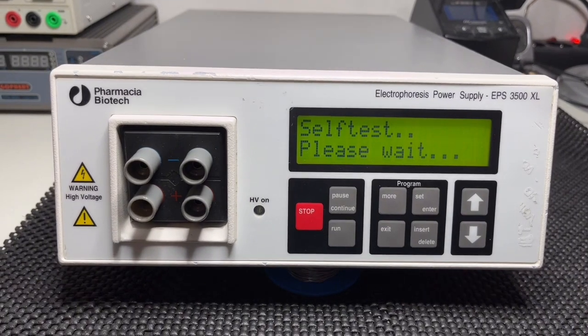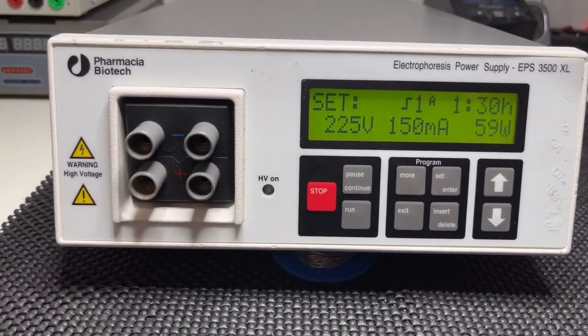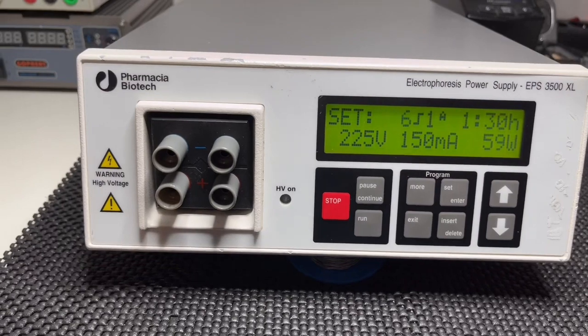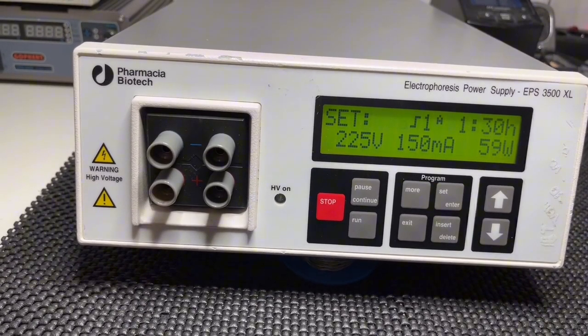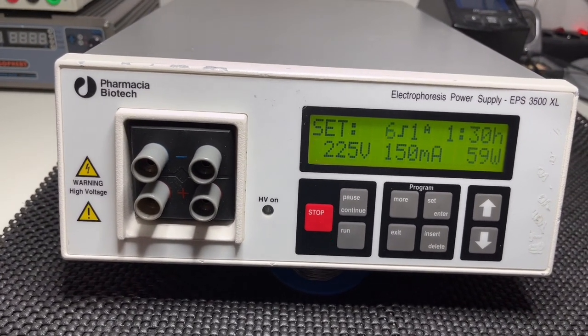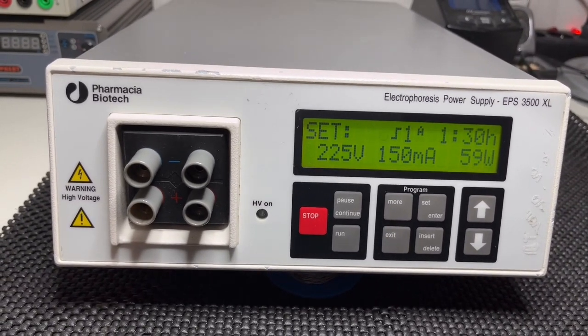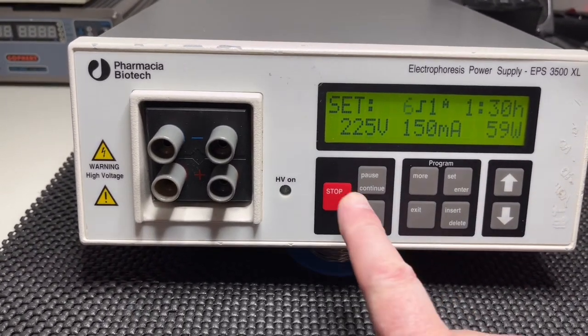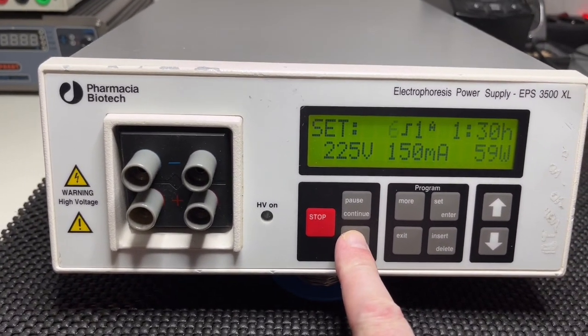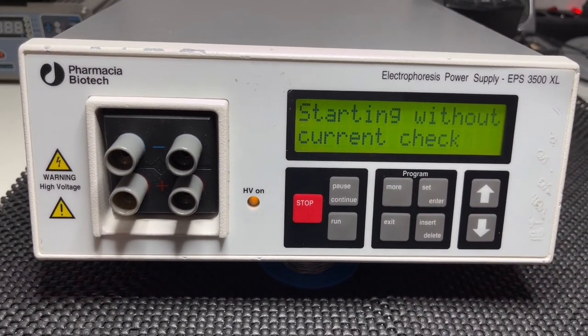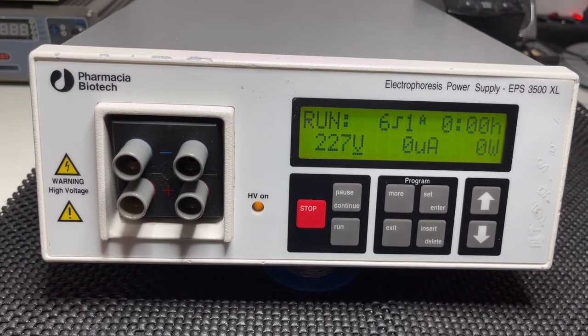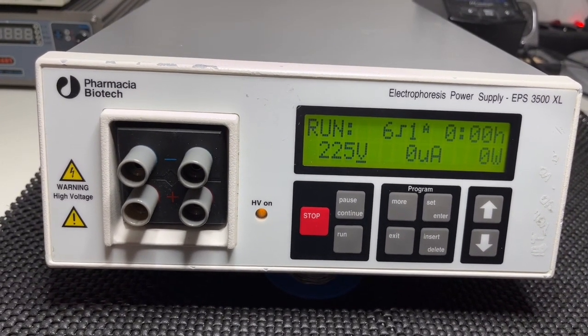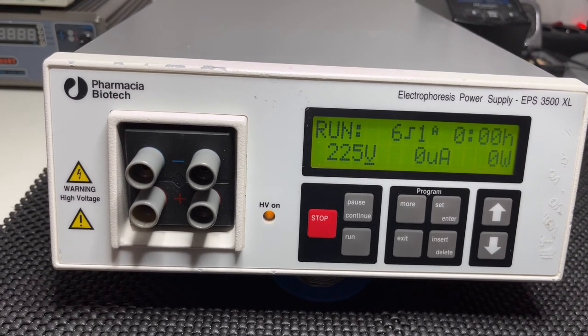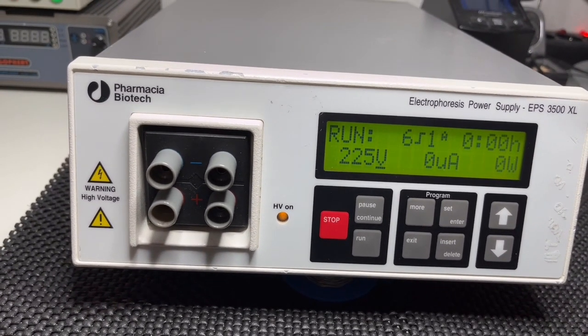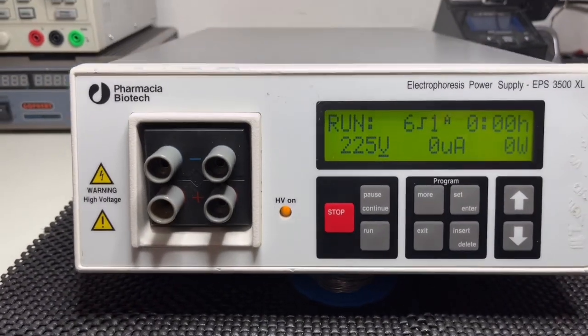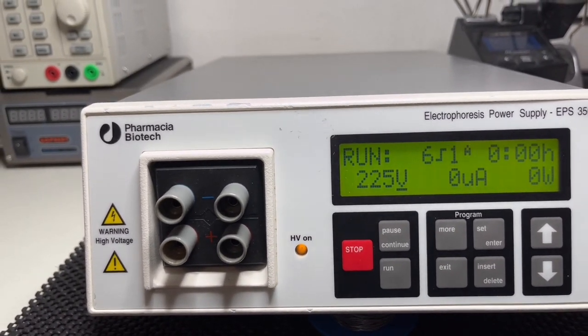Self-test, a very annoying beep, and that's it. For example, I've set the output to 225 volts, 150 milliamps, and 59 watts. If I press the run button, it says that it starts without the load check. That means that all these power supplies have a security feature that will not output high voltage if they do not see a minimum amount of load.